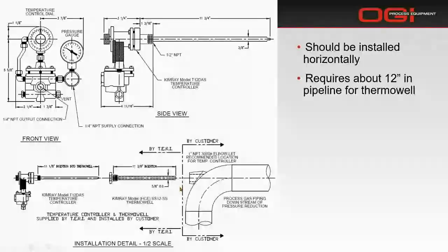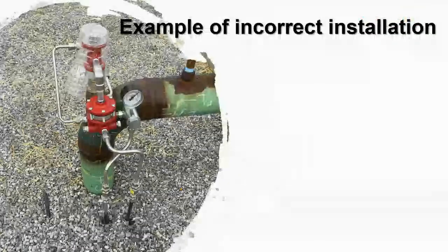And here's an example of an incorrect installation. This is how it's facing upwards. And so again, you could have ice accumulate here and then start breaking down the seal in here. So this is where we custom designed this protective covering. It's an Aquafina bottle. And then we have some tubing that was crossed over, so they had it tubed backwards, and it wouldn't allow this thing to cycle and maintain their bath.